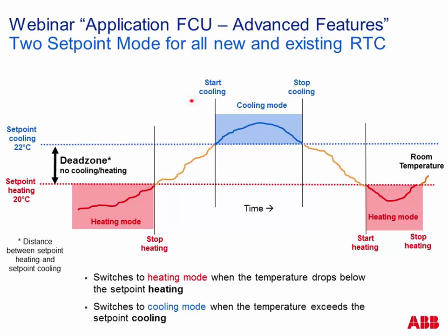One set point and two set point mode. Two set point mode — if you have both heating and cooling — is something we know from the beginning. You adjust two different set points inside the room temperature controller: one for heating, for example 20 degrees, and 22 for cooling. In between there is a dead zone — neither heating nor cooling. Only below 20 degrees is heating active; only above 22 degrees is cooling active. When temperature drops below 22, no cooling; only below 20 does heating start again. The user sees two different set points depending on mode, which can sometimes confuse them.